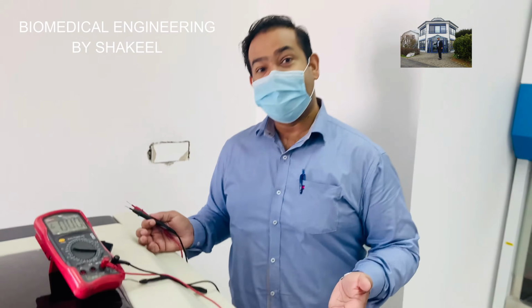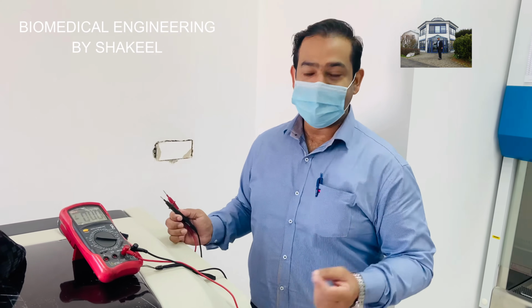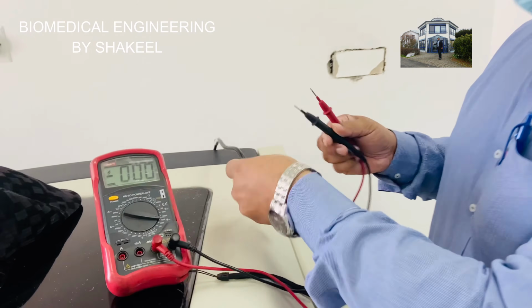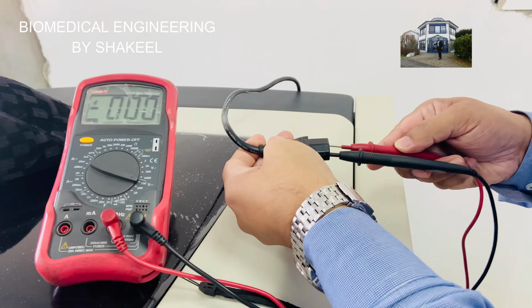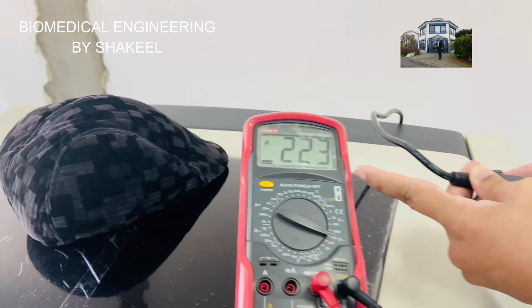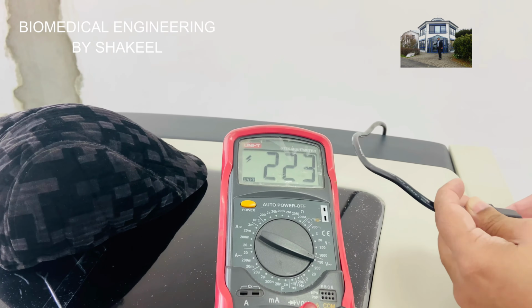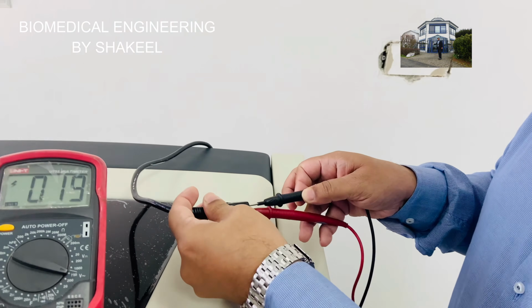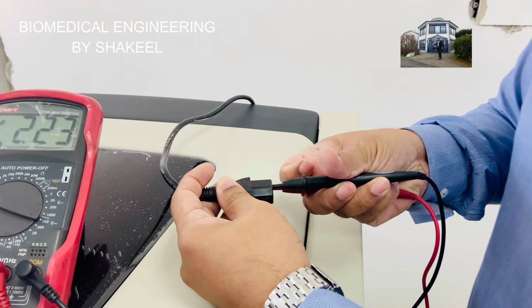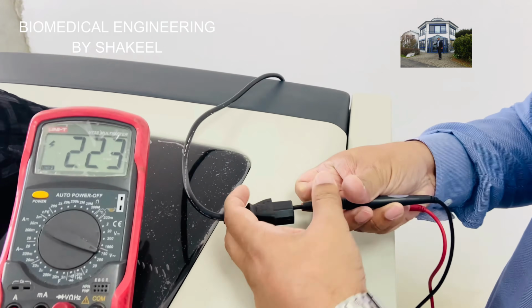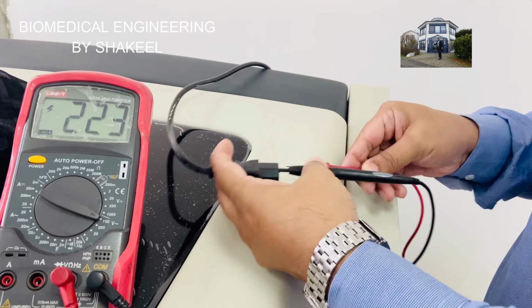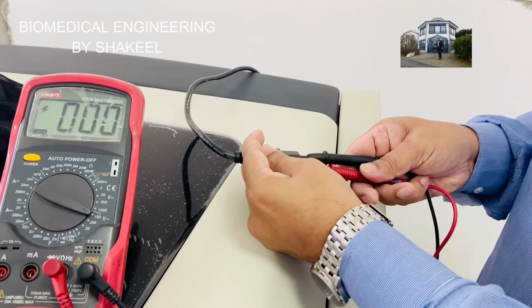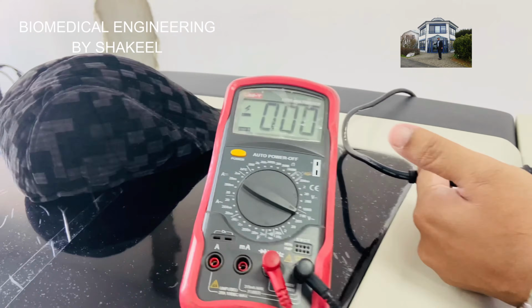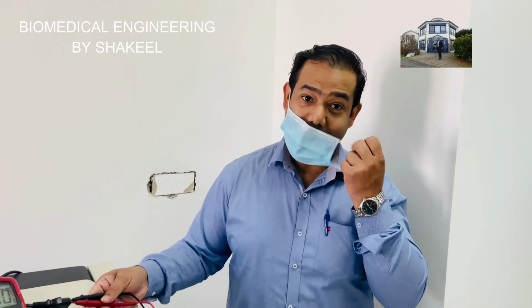Okay guys, before I start the machine, let's check the input voltages. So this is the cable. First, let me check the voltages. So you can see that this is 223. Very good voltages. Okay, next, let me check between the ground and the phase. So this one is also 223. And let me check the ground. So grounding wise, you can see that it is exactly 0. So you can see that all the voltages are very good. So I'm going to start this machine now.